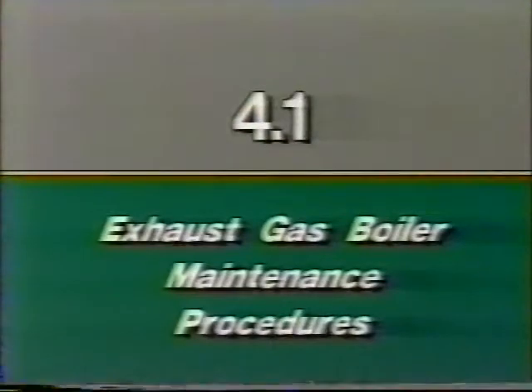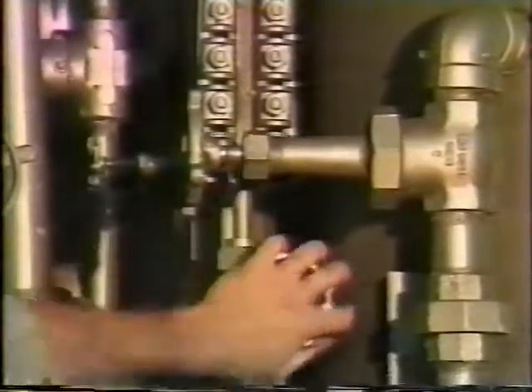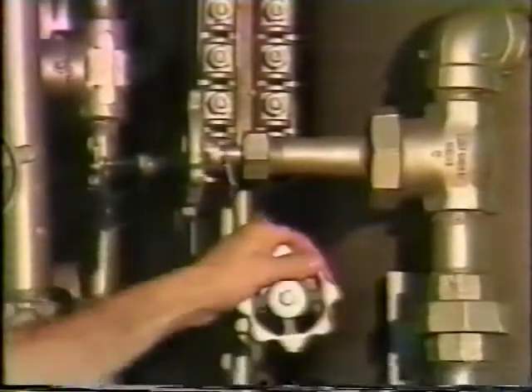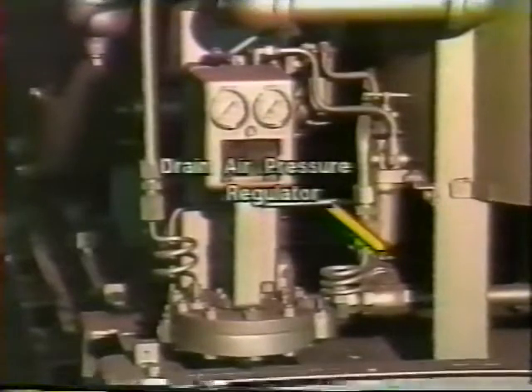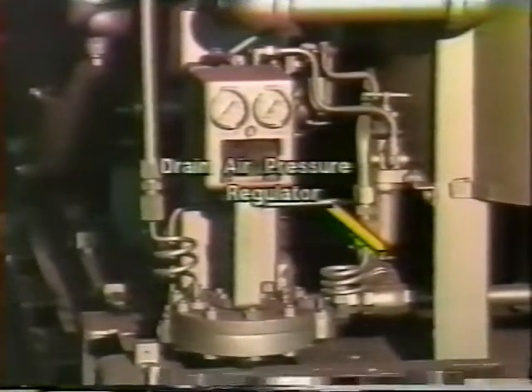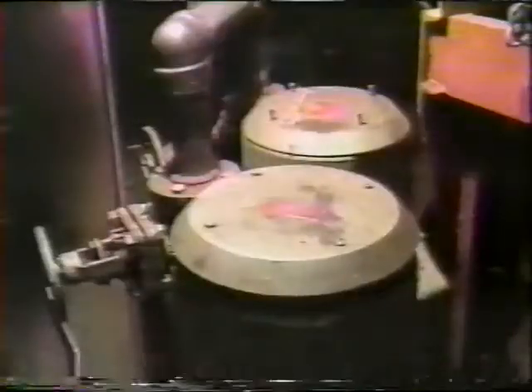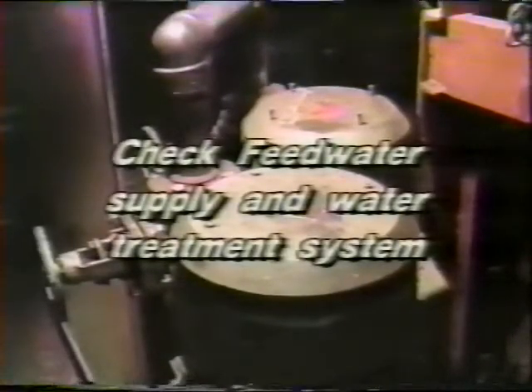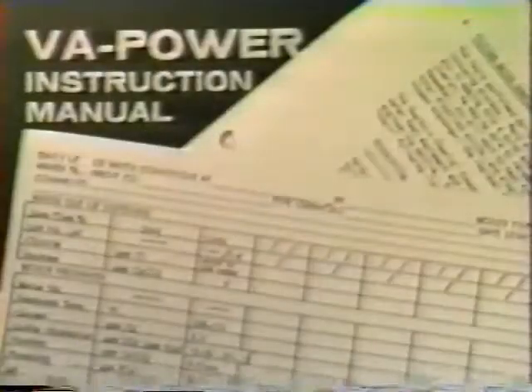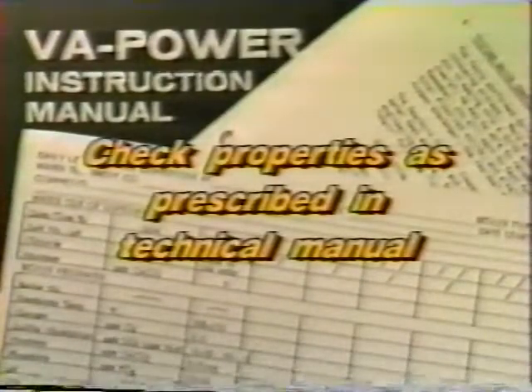Section 4. Maintenance. Exhaust gas boiler maintenance procedures. Maintenance activities should be performed regularly as prescribed in the VA-Power Technical Manual. Perform blowdown of the water level control and the sight glass daily. The drip well sump of the air pressure regulator also should be drained once a day. The feed water supply and water treatment system should be checked for proper operation, and feed water properties should be checked daily according to the procedure described in the tech manual.